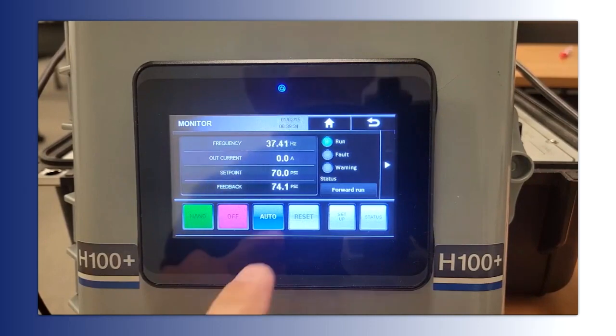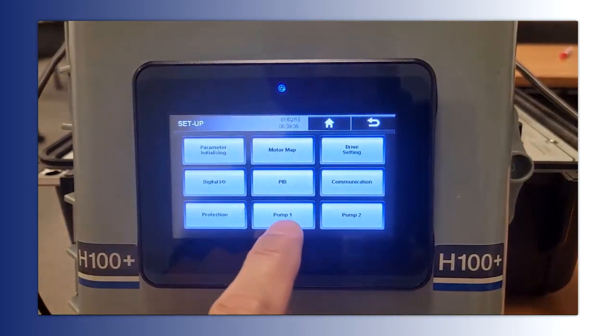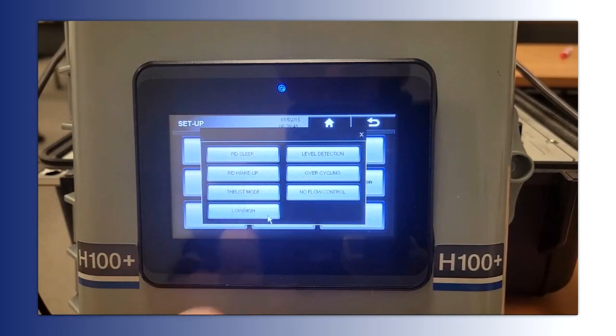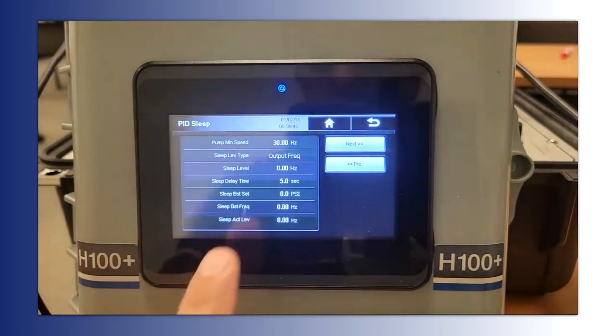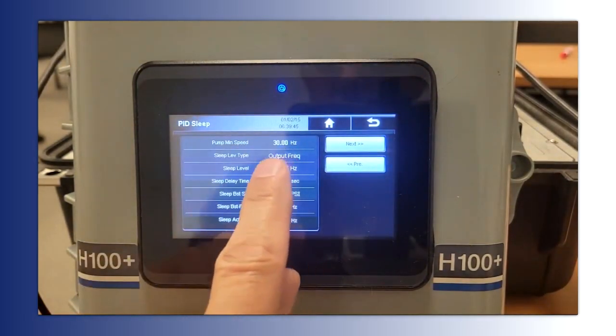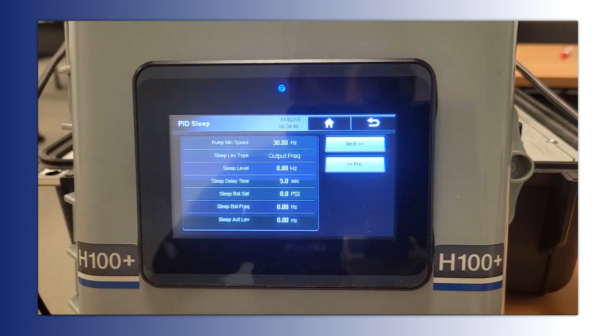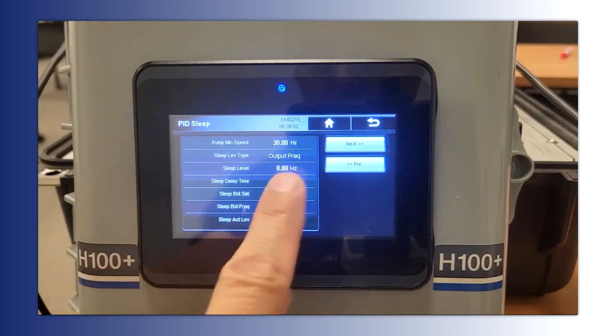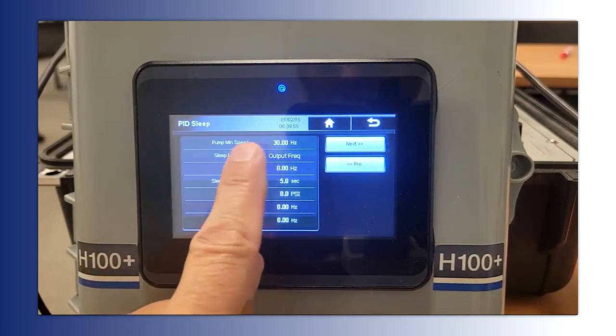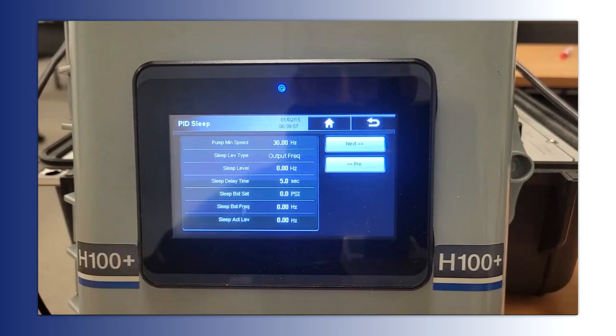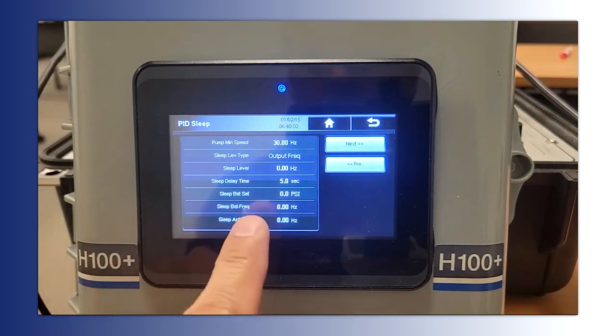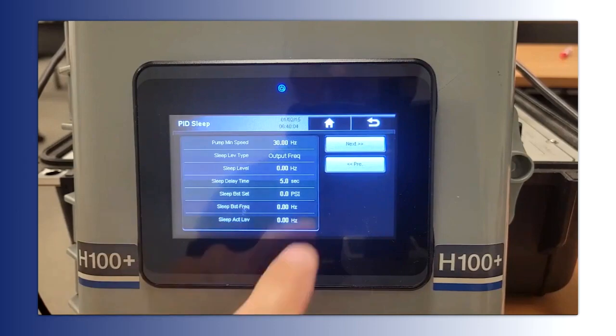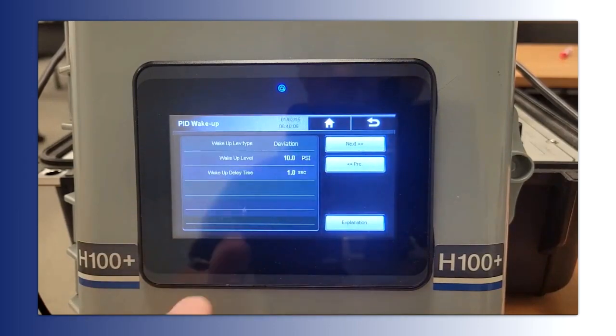So while that's ramping down, let's go to our setup and let's go to pump 1 settings, and we see we have our PID sleep and wake up, which are some other items we talked about. So sleep is 30 hertz. So minimum pump speed is also 30 hertz. So whichever one of these is higher, that's your sleep level. So actually sleep level is at 0, and then minimum pump speed is 30 hertz. So that 30 hertz becomes your sleep level essentially. There's a 5-second delay, and then there's a sleep boost, which typically I don't set up.